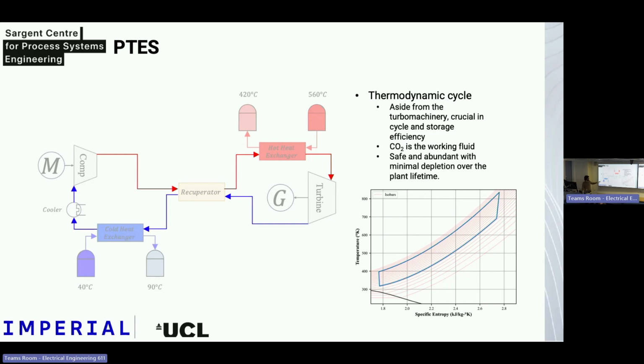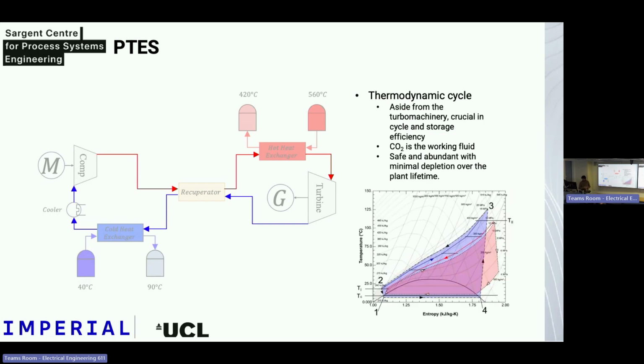Another advantage of this cycle, which I'll compare with another cycle in a moment, is that we can have sensible heat storage on both sides, or mostly on the cold side, so that we don't have phase change in the carbon dioxide or the working fluid on the cold side. Comparing that to a transcritical cycle, for example, there's phase change on the cold side, so we'd need to store it as a phase change material, like an ice slurry or something similar. That limits the available technologies for us on the cold side, so it is beneficial to operate in the supercritical region.